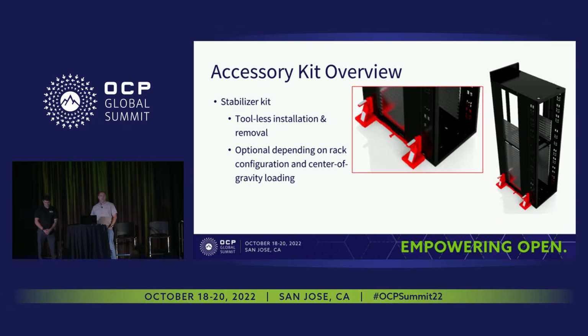Another accessory kit which will be ready as we roll into mass production is the stabilizer kit for the racks. We've got a lot of gear in these racks, and they're extremely heavy when fully configured and loaded. In certain configurations, depending on the type of gear and where we put it in the rack, the center of gravity could be higher than what's acceptable from safety limits as we're pushing the rack around throughout the data halls or at our integration sites. So we have a toolless stabilizer kit which can be added to either side of the rack just to increase that overall footprint and provide a more stable base for the rack as we're moving it around.